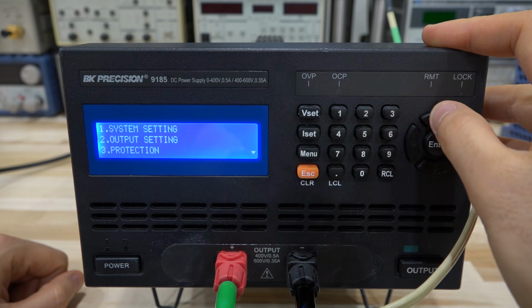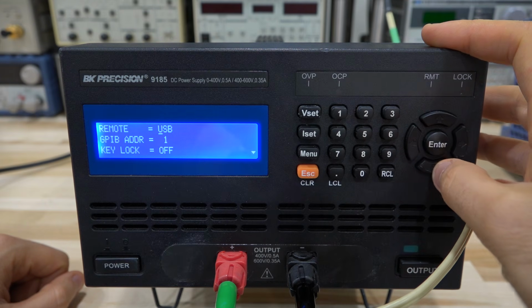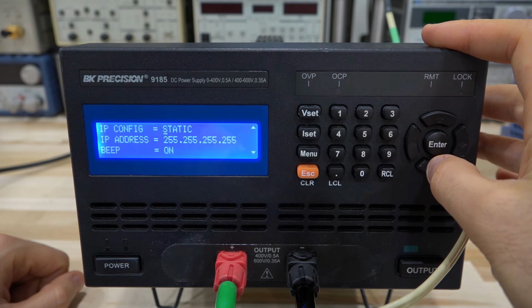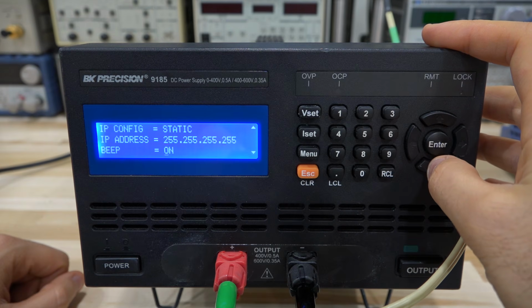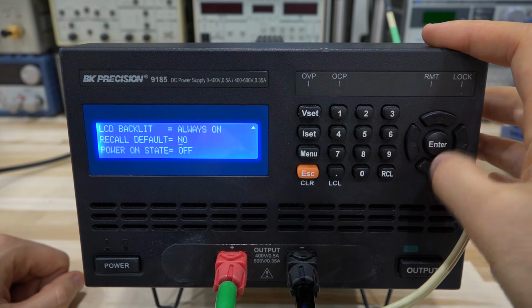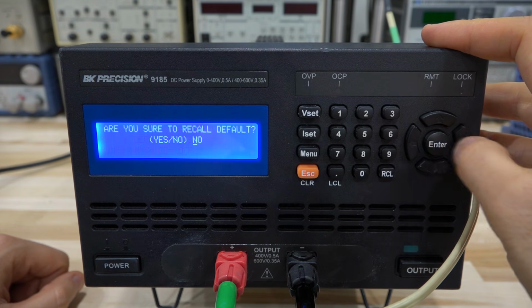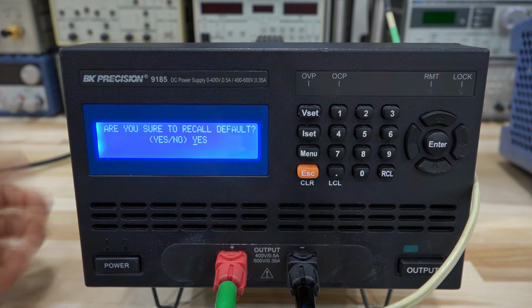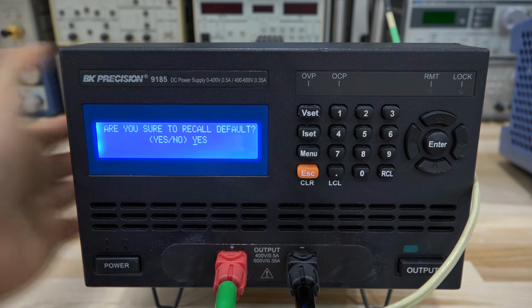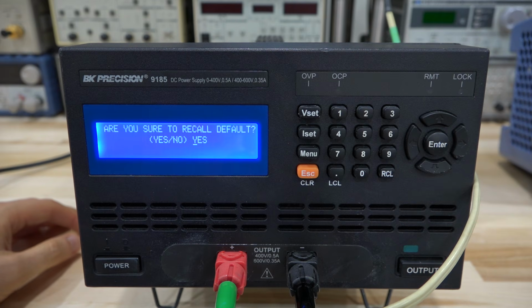So first thing to do is perhaps reset the instrument. There's IP address, and so on. We don't need that. Where is it? There it is, reset. Recall default. Do I want to do that? Yes. So now it's going to get all the default values back, and then we can go through the calibration menu and see how it does the calibration.